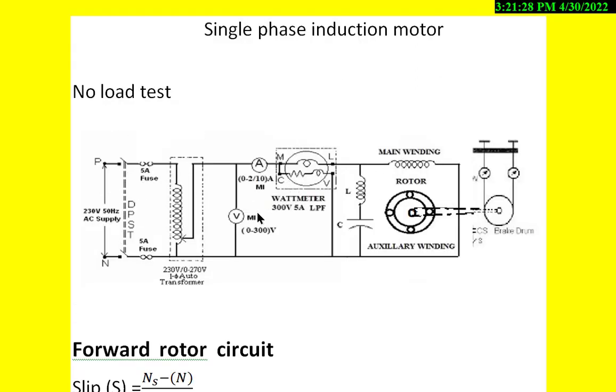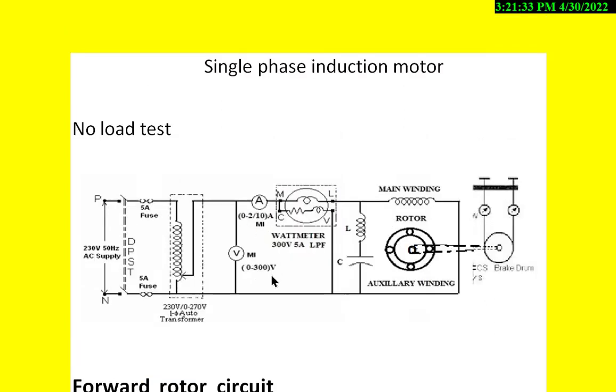For the no load test, the voltmeter rating should be the rated value, that is 0 to 300 volts range, and the ammeter rating should be 0 to 2 amperes, and the wattmeter should be a low power factor wattmeter, and we should apply the rated voltage by using this auto transformer, and note down all the meter readings, keeping the rotor without load. That completes the no load test.